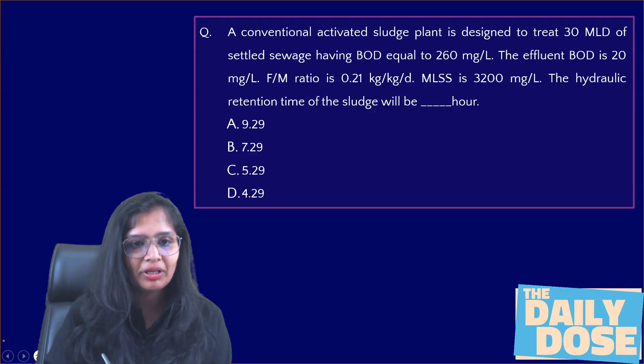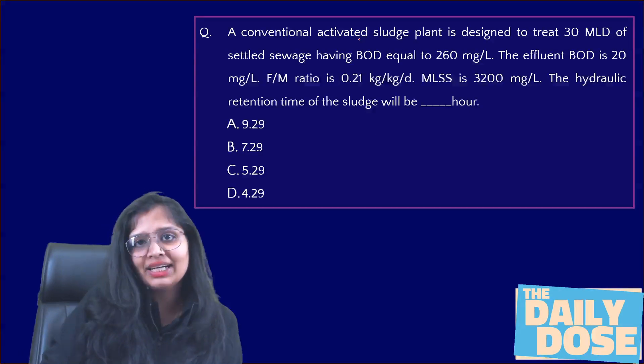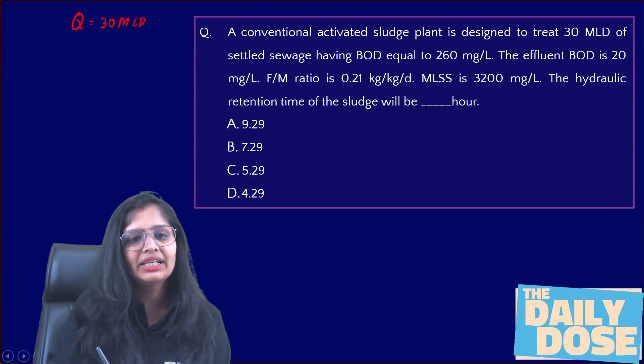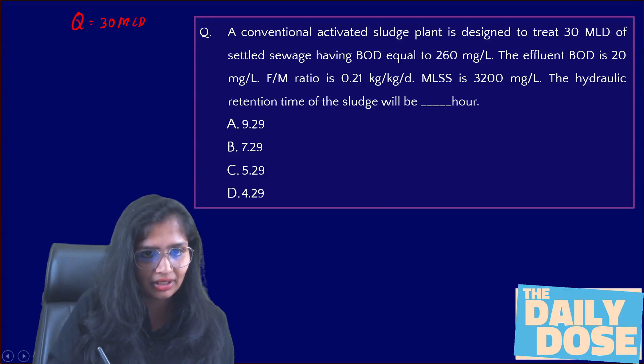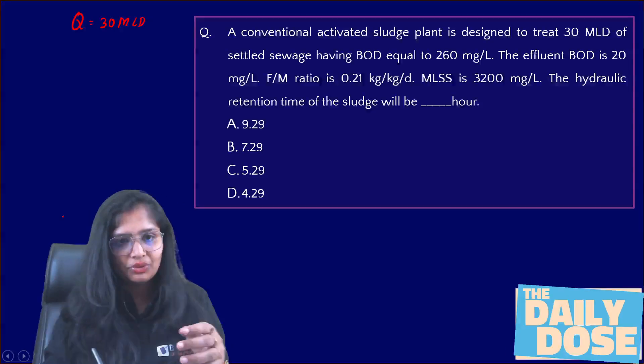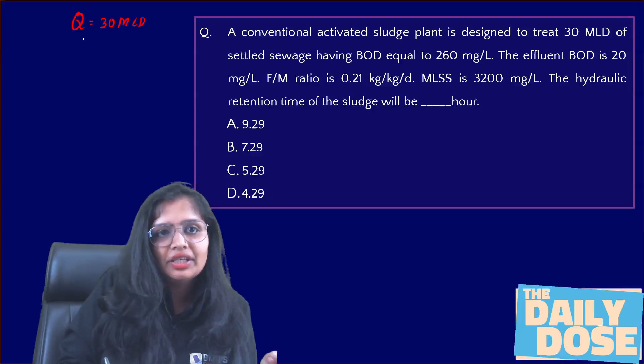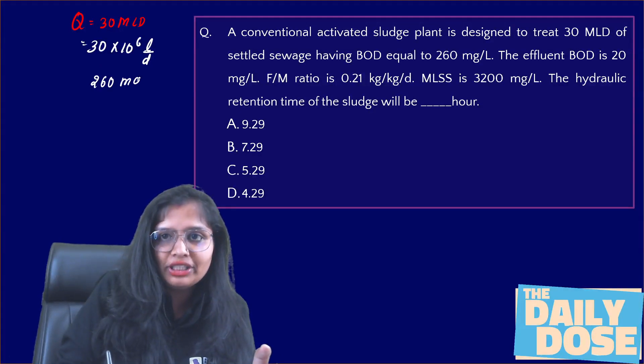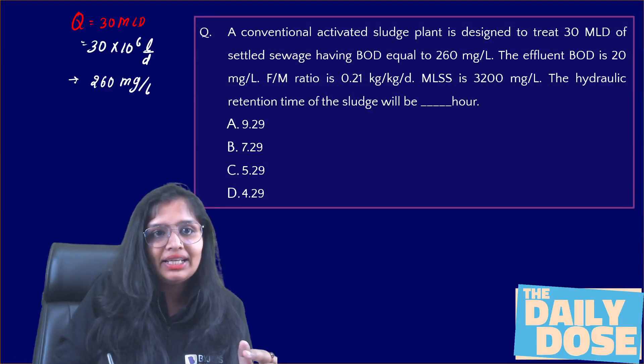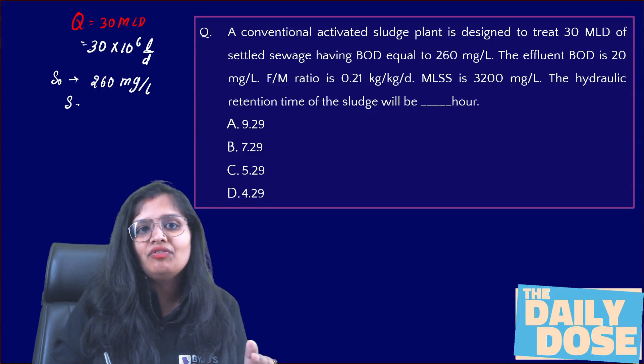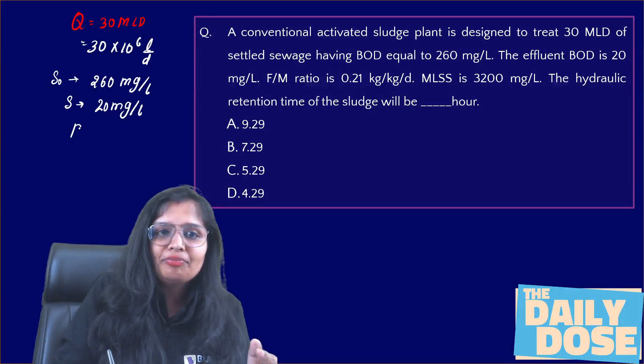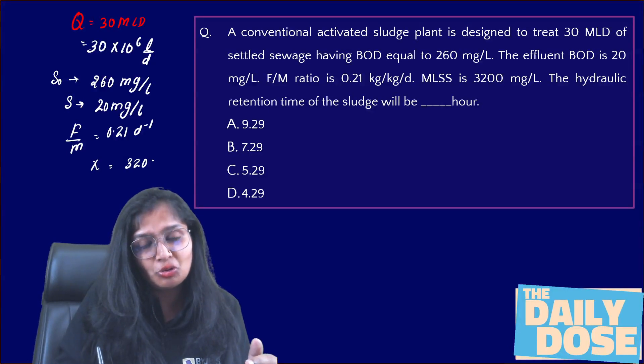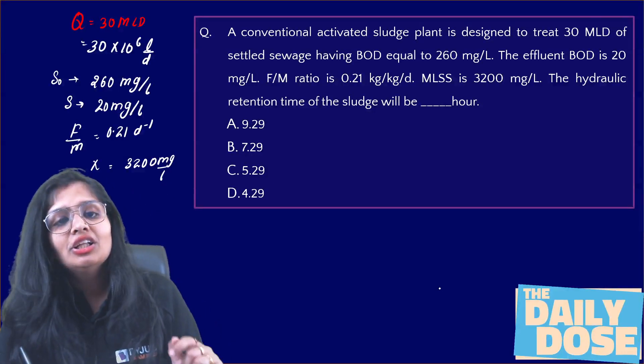First, read the question before I solve it. In this question, a conventional activated sludge plant is designed for 30 MLD water — that is 30 × 10⁶ litres per day. The BOD coming in is 260 mg/L, and the BOD coming out is 20 mg/L. The F/M ratio is 0.21 per day inverse, and the MLSS concentration — which we call X, the microorganisms — is 3200 mg/L. What is asked is the hydraulic retention time.